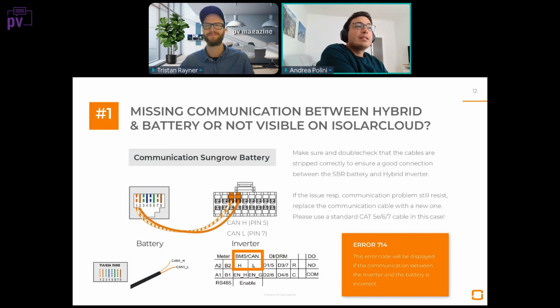Basically, if you take a normal Cat5e cable, they are pin number 1 and 2 on this normal Cat5e cable. So on the battery side, you just need to connect the Cat5e cable to the RJ45 connector. And then, of course, when connecting to the three-phase hybrid inverter, you need to break the cable. So open the cable on the other side, and then take the white, orange, and orange wire and connect them to pin 5 and pin 7 of the inverter.